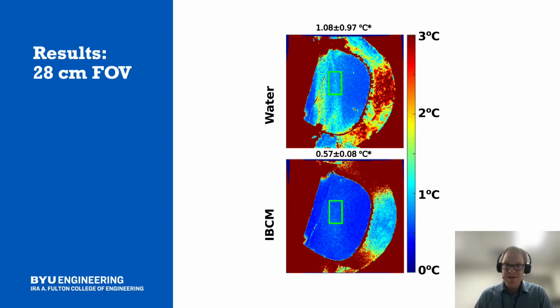On to the results. This figure maps pixel-wise temperature precision that we observed in the phantom for both water and the iron-based coupling medium. The average and standard deviation values for these pixels within the green bounding boxes are also reported. As expected, continuous water circulation introduces time-varying motion artifacts that create spatially varying increases in temperature uncertainty. Some regions experience uncertainties as high as 3 degrees Celsius.